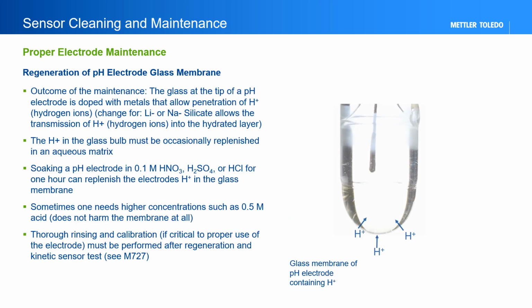The glass tip of a pH electrode is doped with metal ions that allow the conductance of hydrogen ions, as well as a gel layer of hydrogen ions on the bulb. These hydrogen ions can become depleted with use, especially in caustic or non-aqueous solutions, and need to be replenished. Similar to the slow recharge of storing a pH electrode in a pH 4 buffer, a stronger solution can be used for more powerful recharging. Stirring or storing the electrode in a solution of approximately 0.1 molar acid can thoroughly recharge the bulb. It is very important to thoroughly rinse the electrode with DI water after recharging and perform another calibration if calibration is needed for proper use.